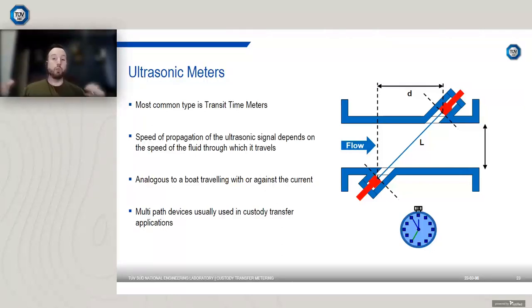Well, you've got a pair of transducers, and what they do is they measure the transit time of ultrasound from one transducer to the other. So the speed of the ultrasound is dependent on the speed of the fluid which it's traveling across. Now, the transit time is measured both going with the flow and going against the flow. A good analogy is like a boat traveling with or against the current.